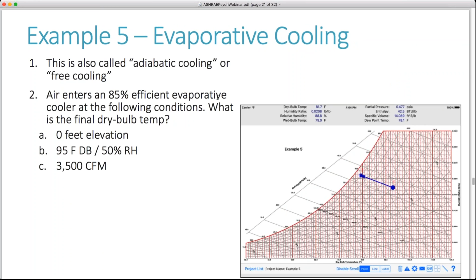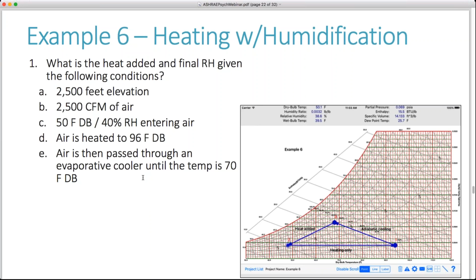Let's look at heating with humidification. Here we're starting to get some more complex examples. What is the heat added and the final relative humidity given the following conditions? We're at 2,500 feet of elevation, 2,500 CFM of air, 50-degree dry bulb, 40% relative humidity of entering air. Air is heated at 96 degrees dry bulb, then passed through an evaporative cooler, or free cooling, until the temperature is 70 degrees dry bulb.